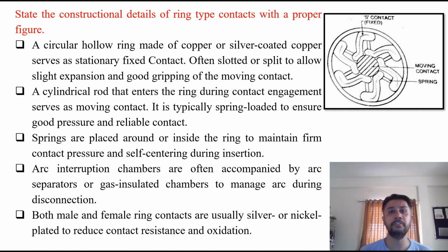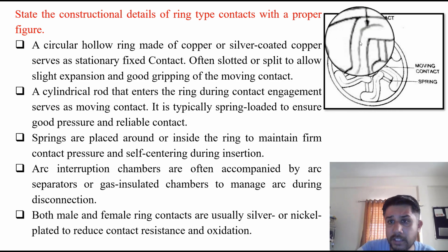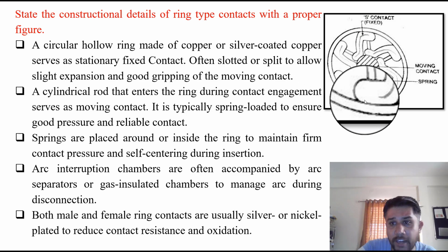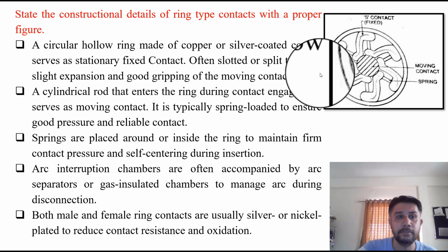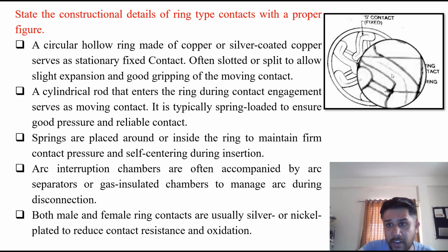The constructional details of ring type contact with a proper figure. So a circular hollow ring made of copper or silver coated copper serves as a stationary fixed contact, often slotted or split to allow slight expansion and good gripping of the moving contact. You can see in the figure, this is the fixed contact, the hollow ring made up of copper or silver coated copper. Often it is slotted, so these are slots 1, 2, 3, 4, 5 and 6. This is where the slotting is done.